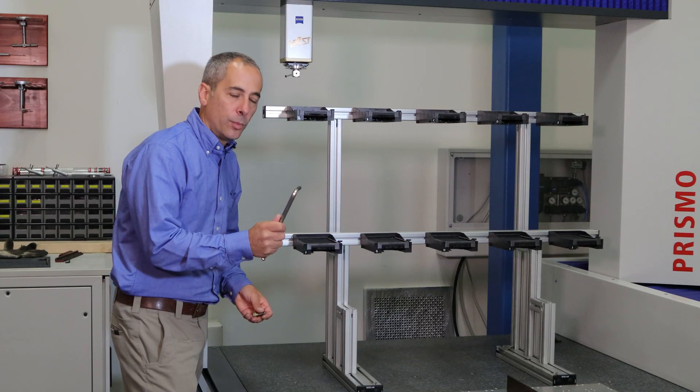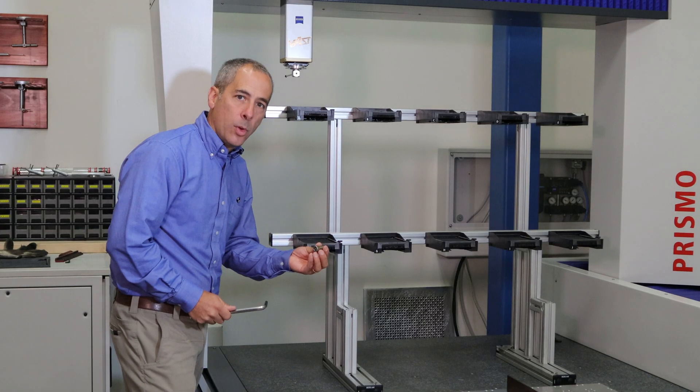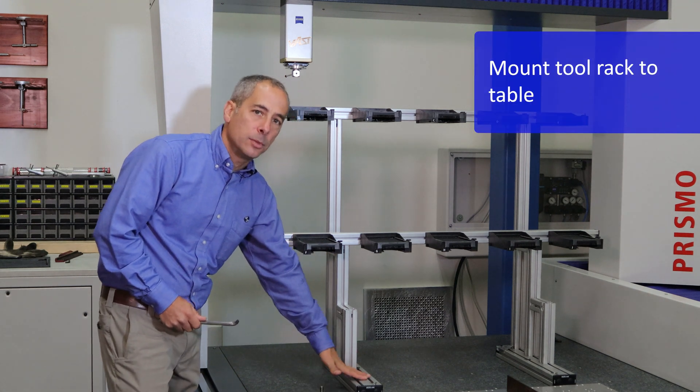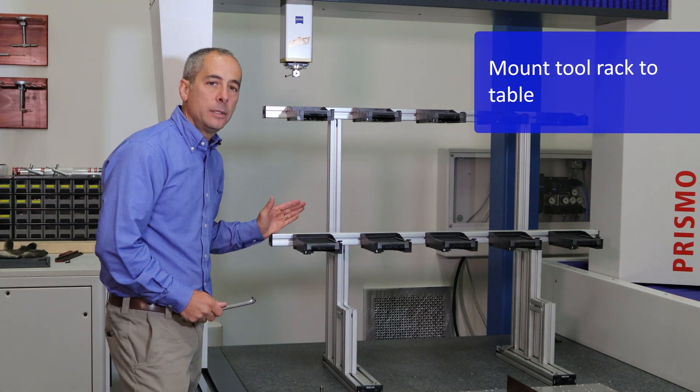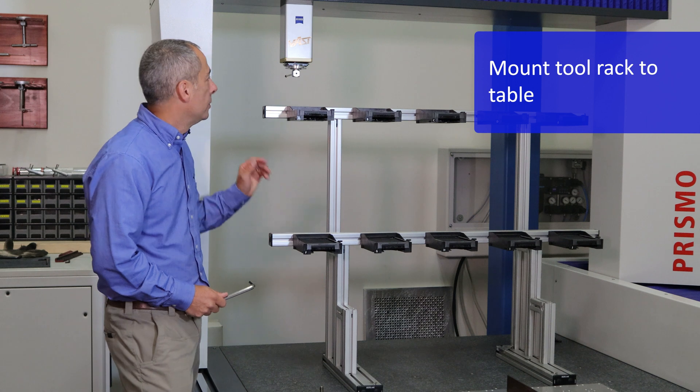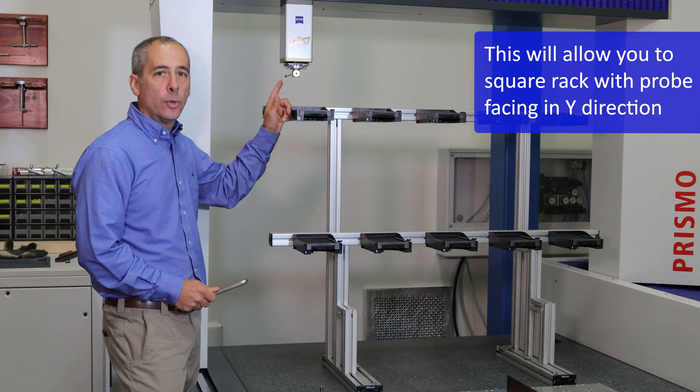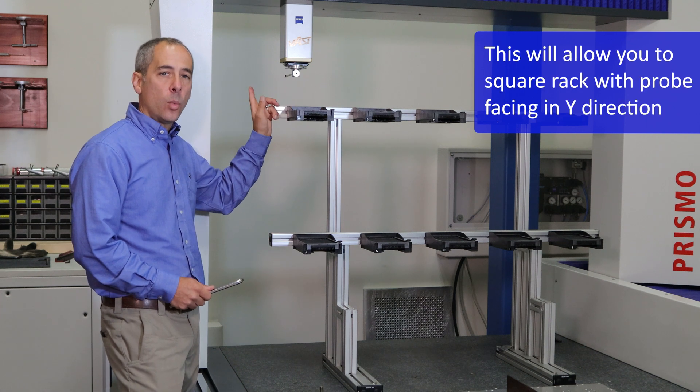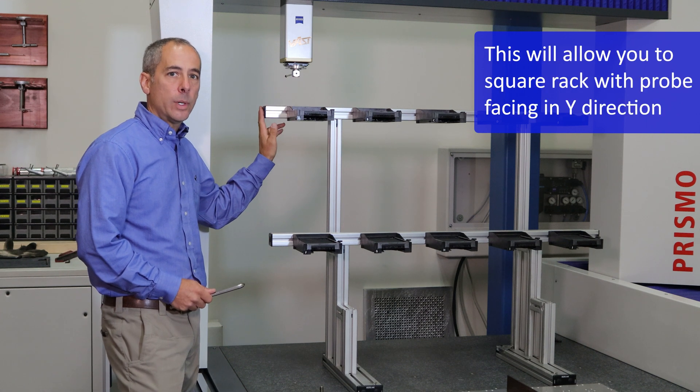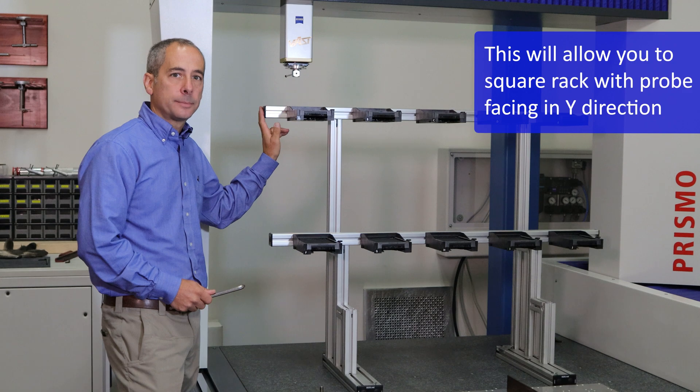Using the wrench and the bolt hardware, mount the tool rack to the granite table as square as you can. From there, we'll use the probe, the points, and the y-axis direction to square the rack.